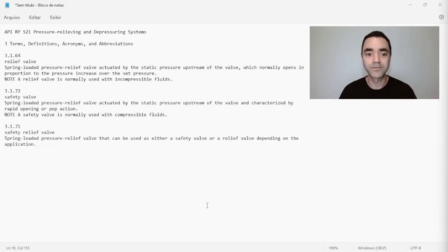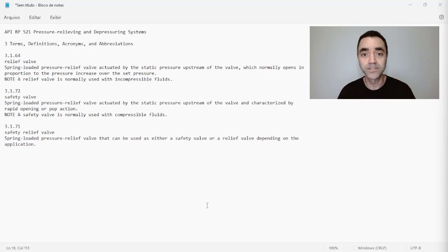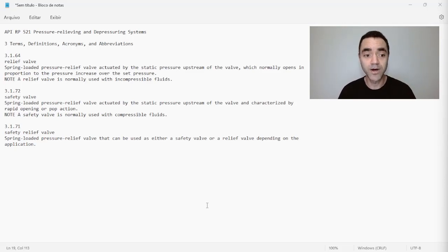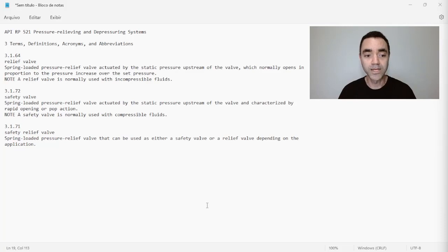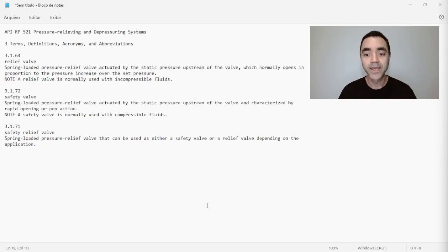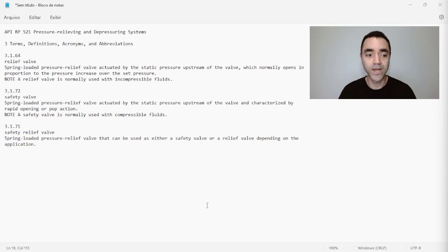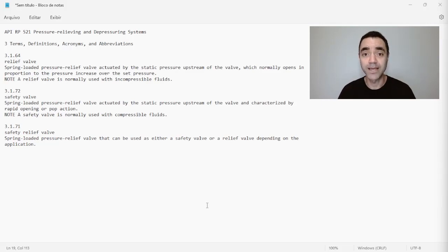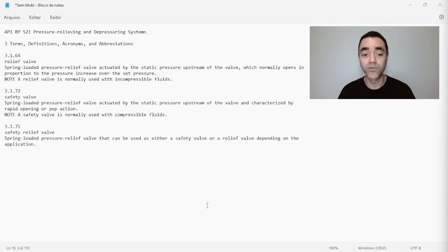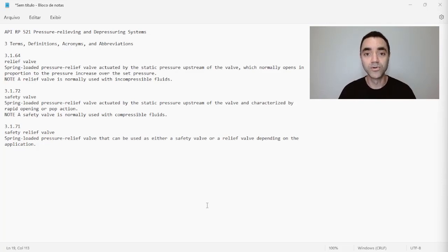So relief valve is a device with a spring loaded that opens based on the action of incompressible fluids according to the API. If we go to safety valve: spring-loaded pressure relief valve actuated by static pressure upstream of the valve, the same description that we have in the relief valve, and characterized by the rapid opening or pop-up action.